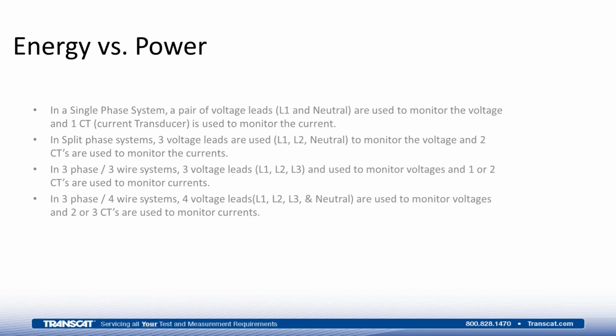But then we would need to employ 2 current transducers, 1 on each of those phases, L1 and L2, to monitor the 2 current loads. Proper equipment that's capable of doing this would then bring those leads into the system and display to you the voltage and the current. And if capable, the equipment could also calculate the wattage being used and display watts, which would be that instantaneous value.